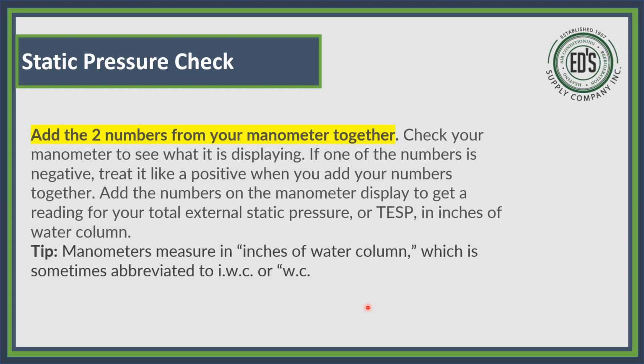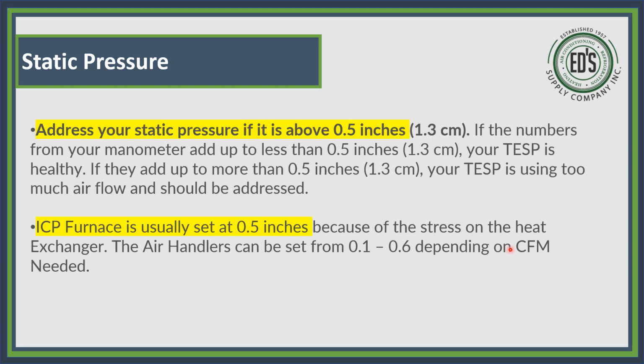On the supply, you want to see 3, 4, 5. 6 is way too much, okay? 5 is borderline too much, because if you're trying to get an overall 0.50, then supply can't be 5. Supply would have to be 4 and return would have to be 1. So if you're seeing a 3 on return and a 3 on supply, I've got to get my return down to at least a 1, so I'm within that 0.50 range. And when you look at some of these install manuals, you're going to see real quick what they have in them. Anything over 0.50 you need to address. And like I told you, you can pinpoint: is it the supply or is it the return?